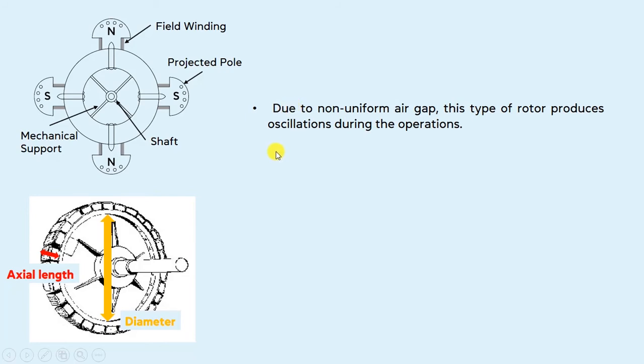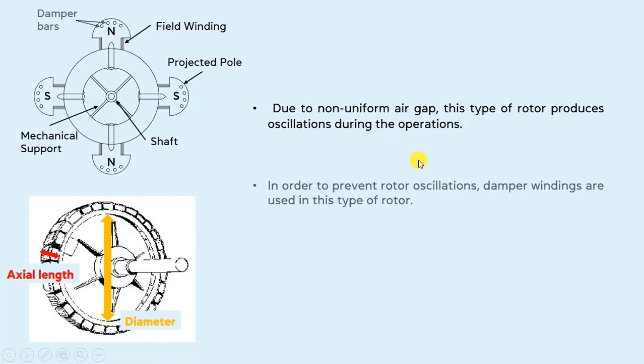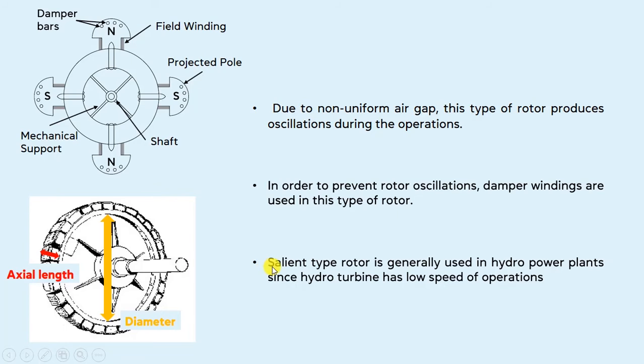Moving forward, due to the non-uniform air gap, this type of rotor produces oscillations during operation. In order to prevent rotor oscillations, damper windings are used. Here you can see damper bars have been provided in the outer poles of the salient type rotor to prevent rotor oscillations. Salient type rotor is generally used in hydro power plants since hydro turbines have a low speed of operation, and as we know, salient type rotors are only used in medium and low speed machines.